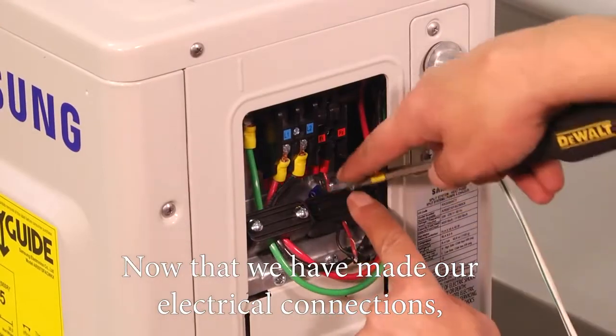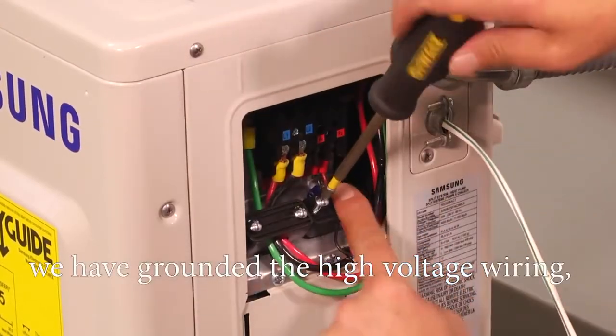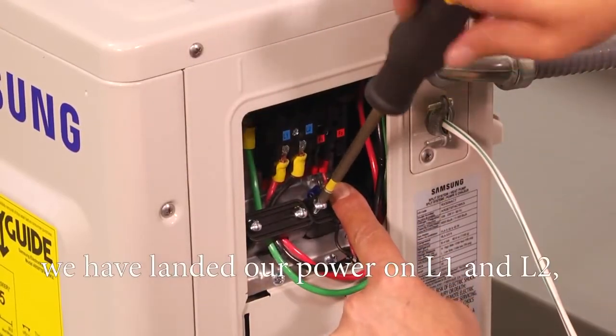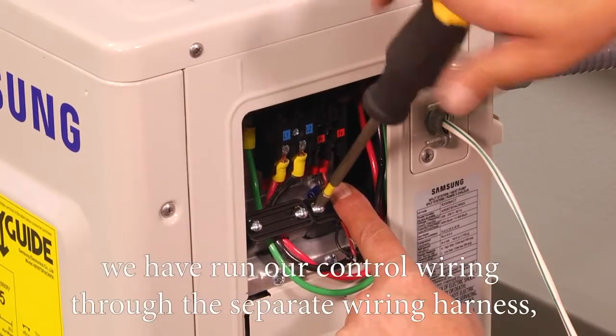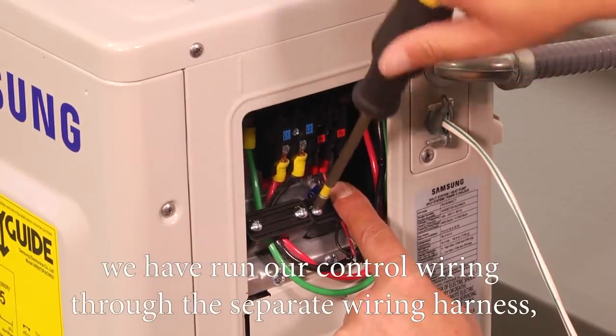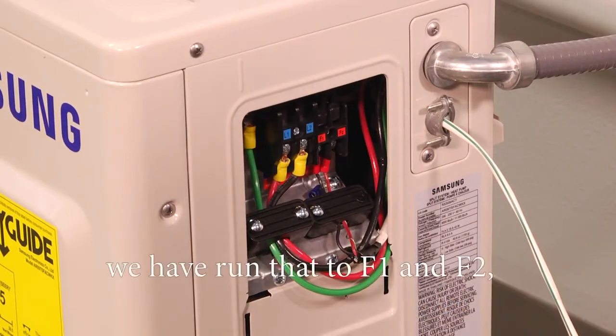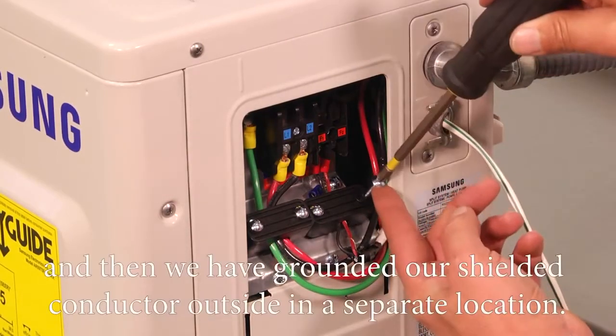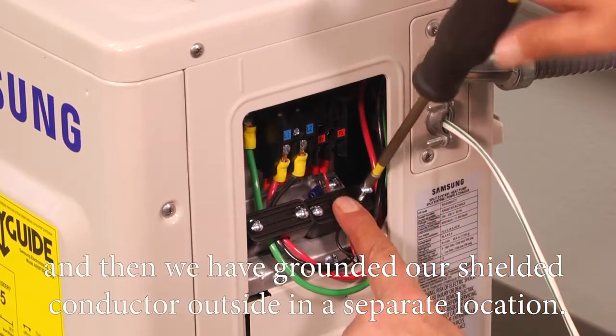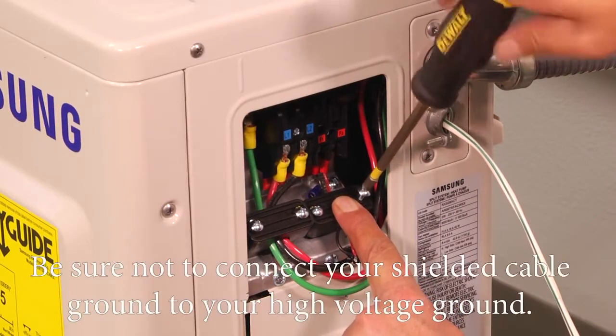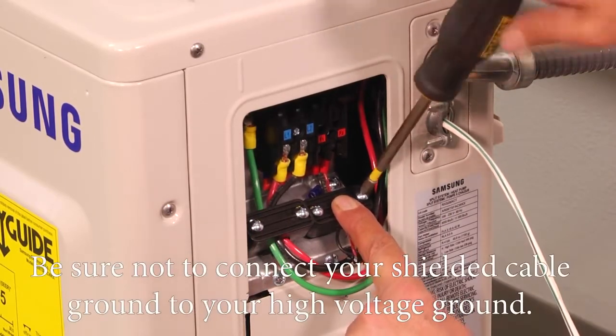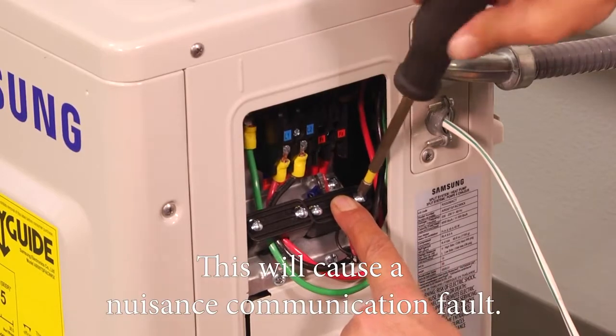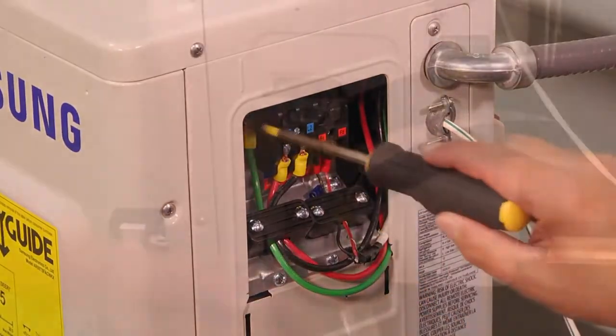So now that we've made our electrical connections, we've grounded the high voltage wiring. We've landed our power on L1 and L2. We've ran our control wiring through the separate wiring harness. We've ran that to F1 and F2. And then we've grounded our shielded conductor outside in a separate location. Be sure not to connect your shielded cable ground to your high voltage ground. This will cause a nuisance communication fault.